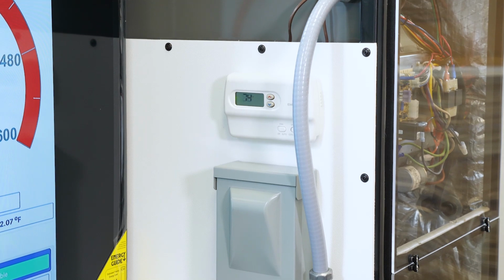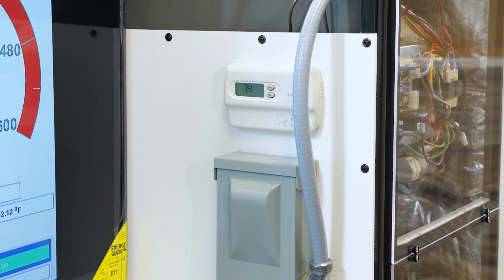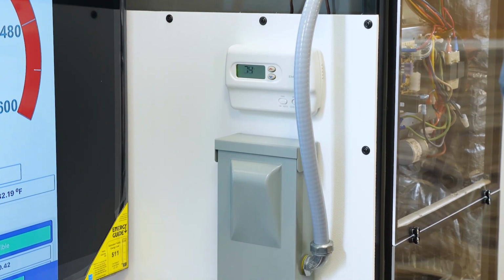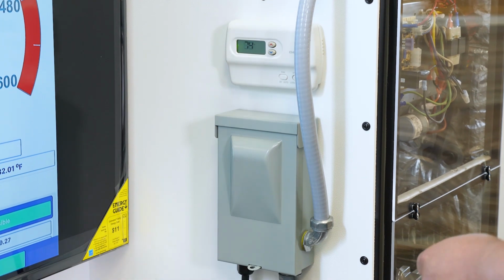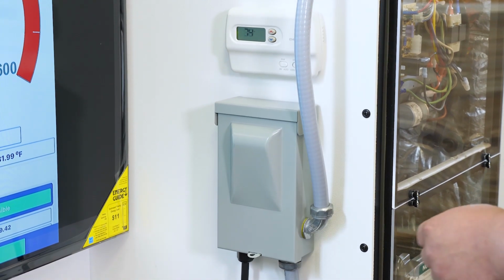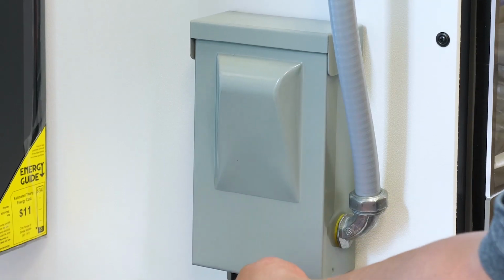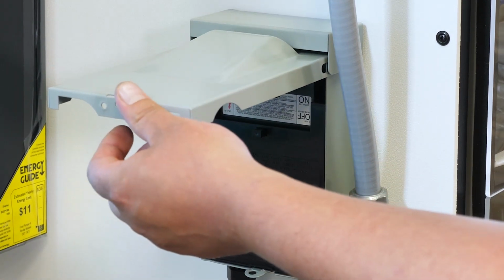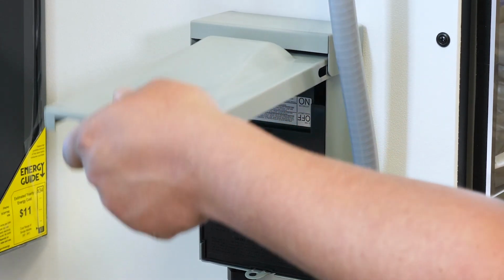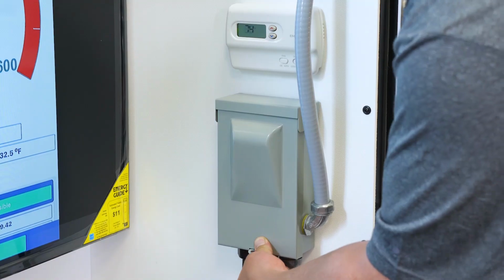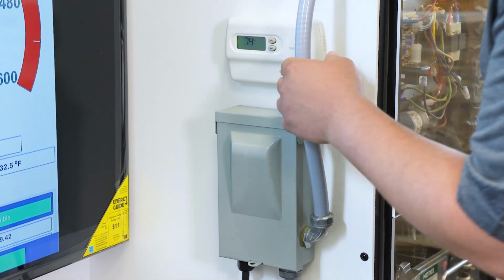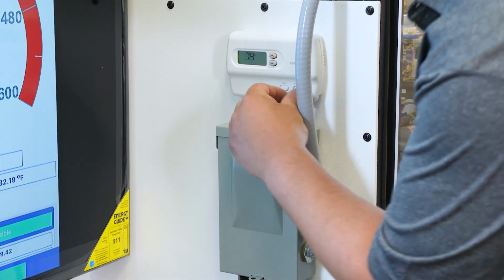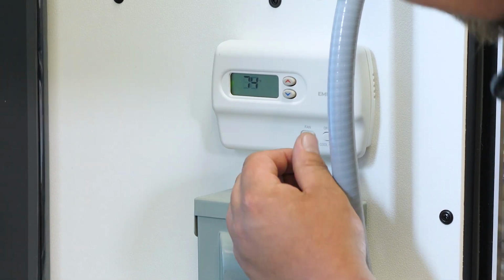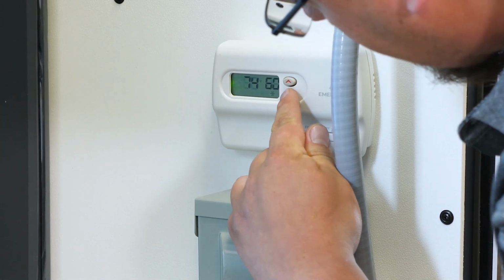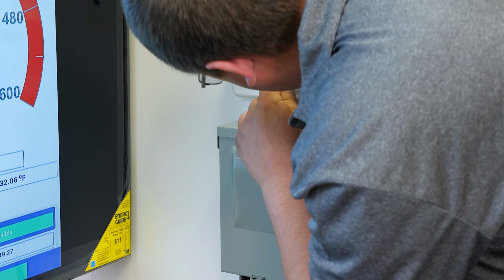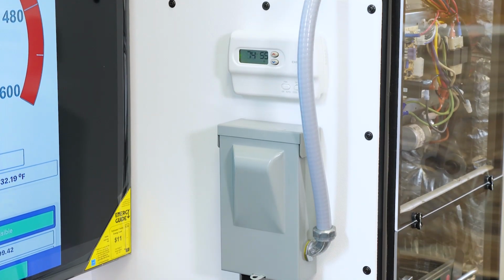So the first time when we go to fire this thing up, we want to make sure that all the fault toggle switches are in the on position, that the blower motor speed control is in the on position. We can double check our fusible disconnect that that's in the on position. Then from our thermostat, we need a call for cool. So I'll flop that over to cool. We'll call for cool.